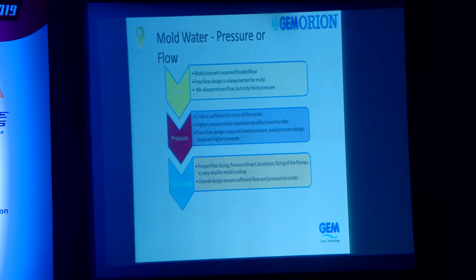Now, I told in the beginning of the presentation that the pipe sizes and pressures are very important. Normally, when we meet a customer and discuss their requirement, there is always a gap between the flow and pressure. People always feel that they need more pressure for their process to operate. But it is a simple physical fact that when we use free flow through the molds as channels, then the pressure requirement comes down, and pump pressure also comes down, which results in very huge savings in power.